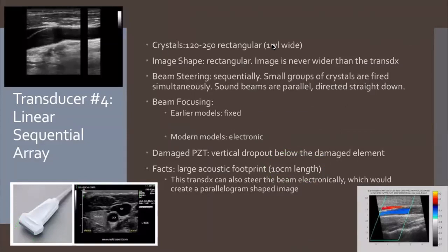Beam steering is done sequentially. So remember, small groups of crystals are fired simultaneously. The sound beams are parallel and going straight down into the body. And so remember, when you hear the word sequential, I want you guys to think small groups, and that'll help you remember it. It's small groups of PZTs that are fired off from one end of the transducer to the other in order. Remember, it's going to give us that really detailed image.